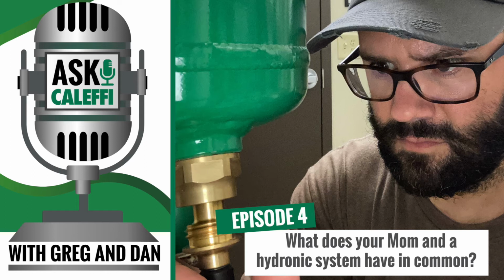Hydronic or chilled water only, closed loop, and potable water systems, they're not multi-pass systems. If you're looking to get rid of debris out of a potable water system, we're always going to tell you, look at a filter. Absolutely. Yeah, that's absolutely the way to go.